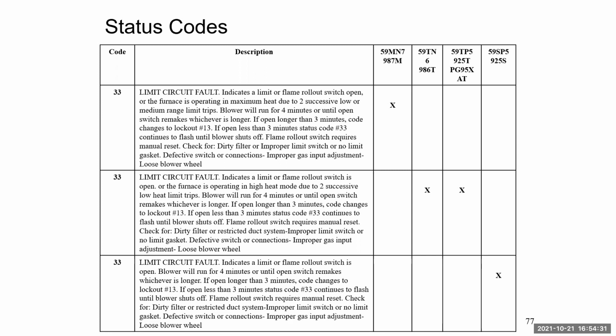This was a big problem. The reason it came about was due to overheating issues with zone systems. Last year, I guess it was a really, really hot year for Carrier in these issues. So they put something in their programming for it. If you get a system that is in limit trip and you are on a zone system, let me back that up. You do not have to have a zone system on this unit in order to have this fault code. It's any system with the UI, but it's honed in on zone systems. If you're on a zone system and it tripped out on zone 1, it's going to open that zone 100%. It's going to open the remainder zones 25%. And it's going to force that thing into high heat, and it's going to sweat your customer out. Carrier's way of doing it this way is they'd rather make you sweat than freeze.